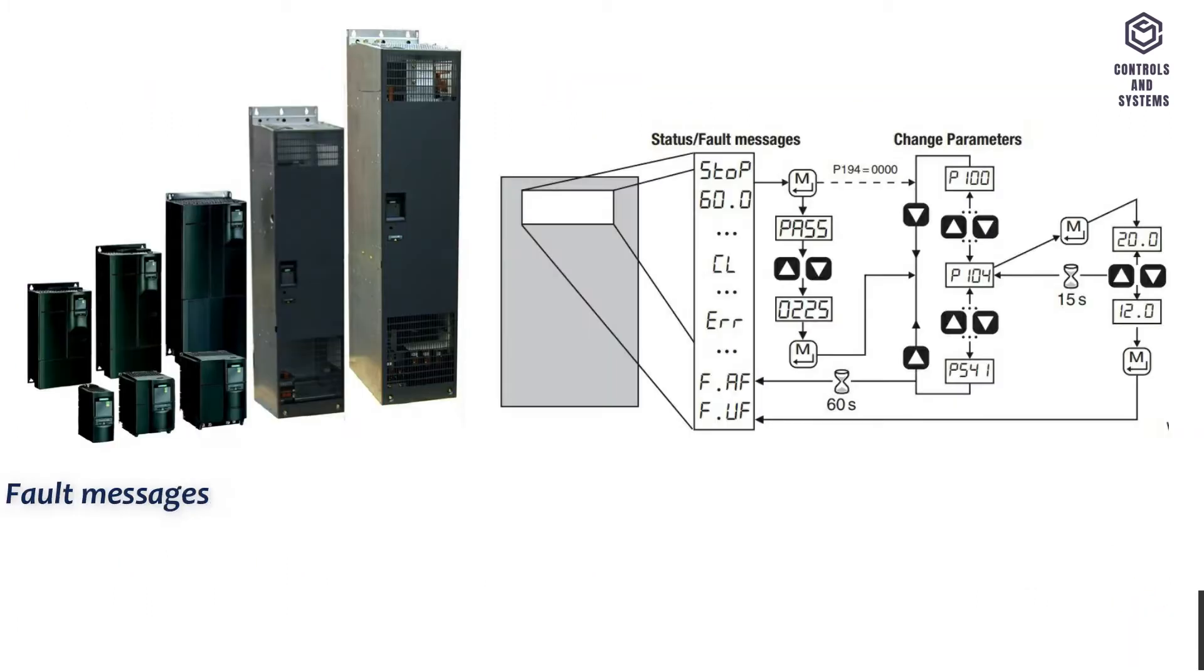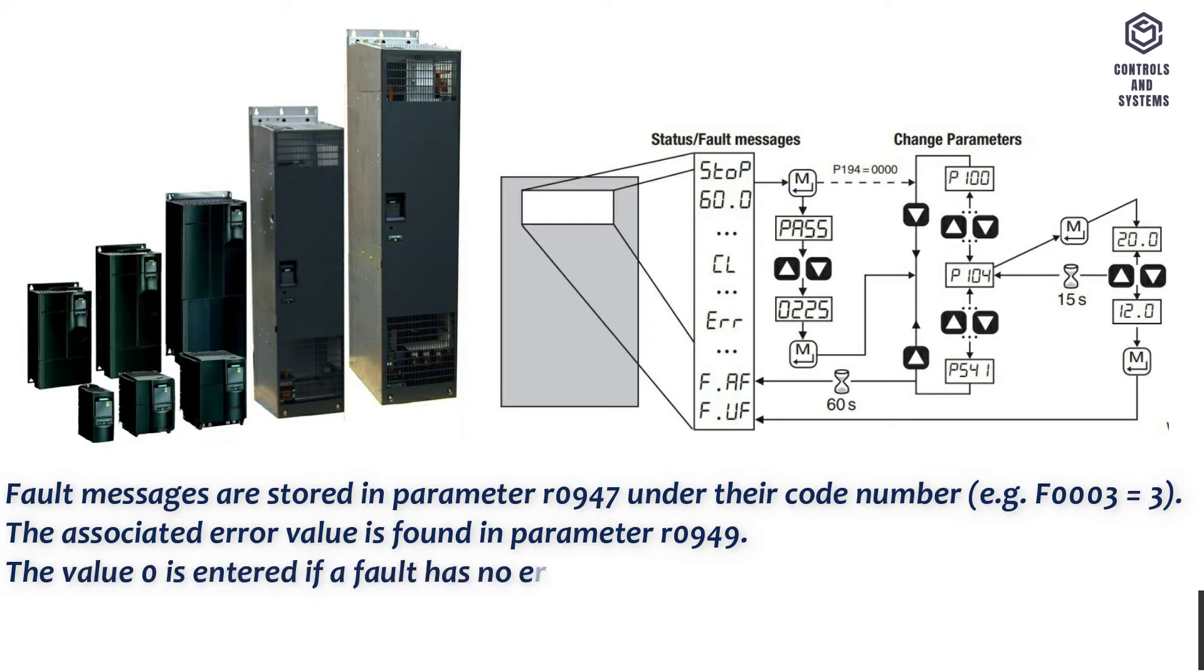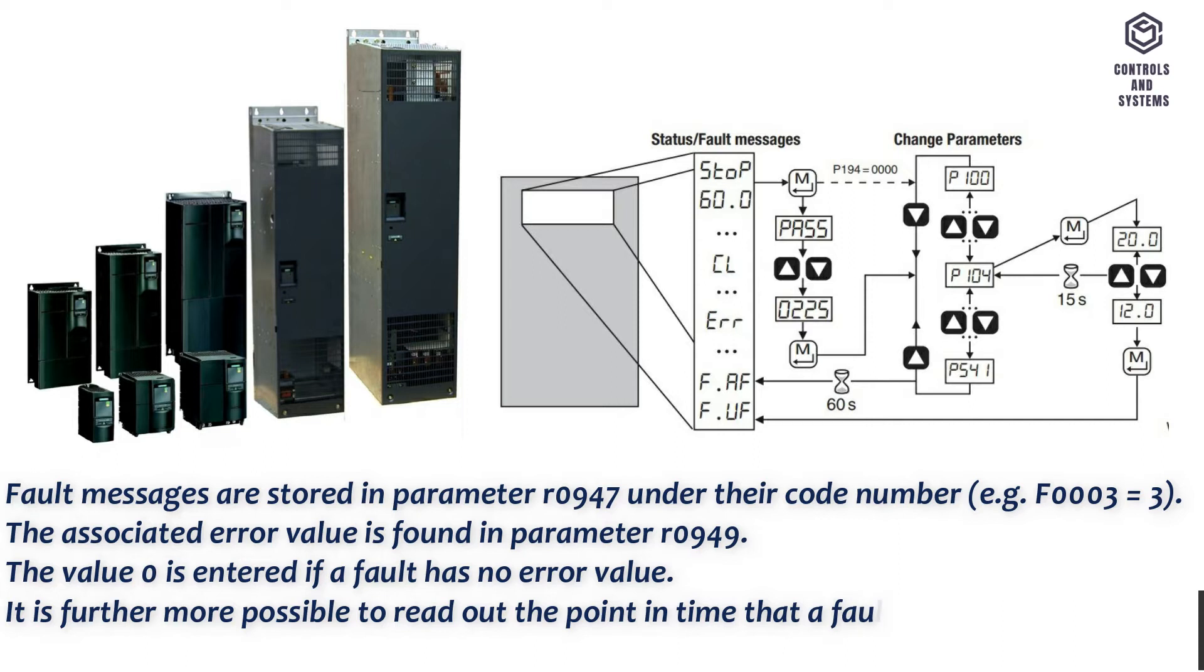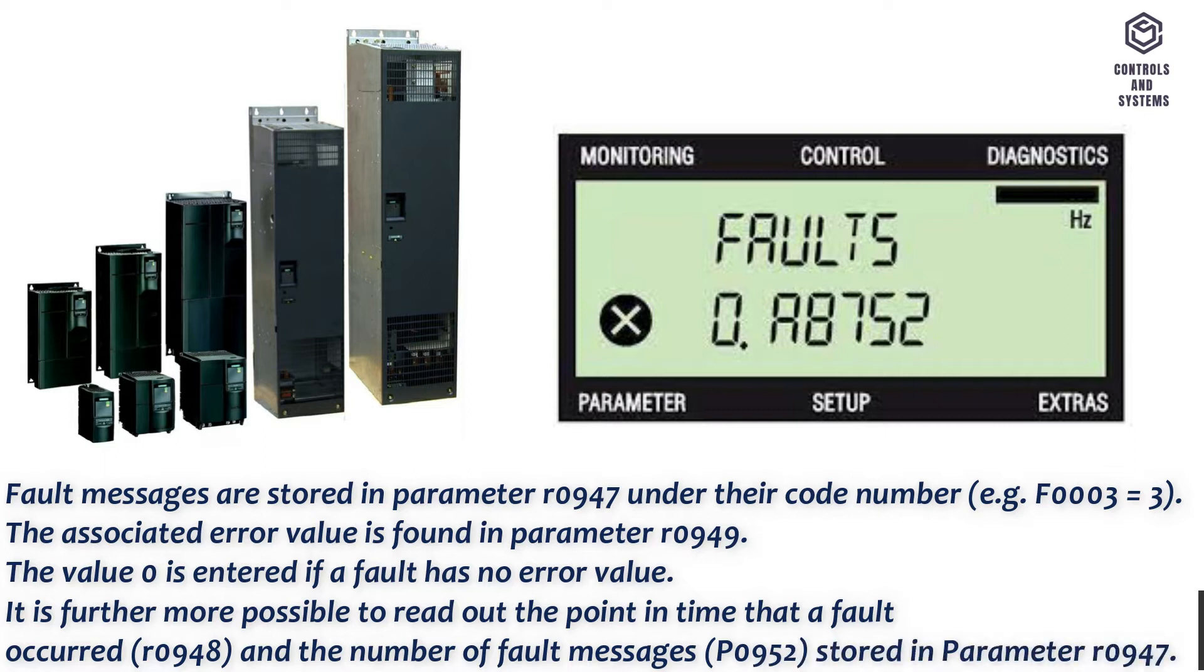Fault messages are stored in parameter R0947 under their code number, for example F0003 equals 3. The associated error value is found in parameter R0949. The value 0 is entered if a fault has no error value. It is furthermore possible to read out the point in time that a fault occurred, R0948, and the number of fault messages, P0952, stored in parameter R0947.